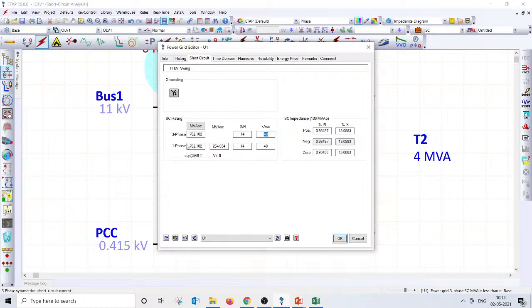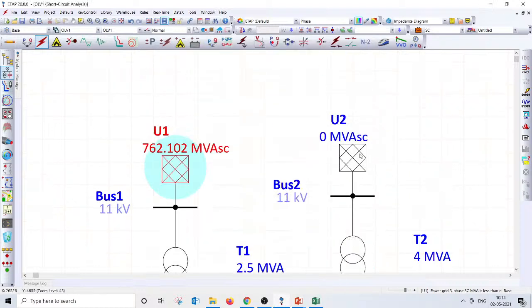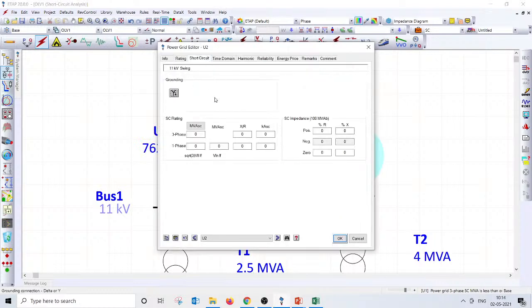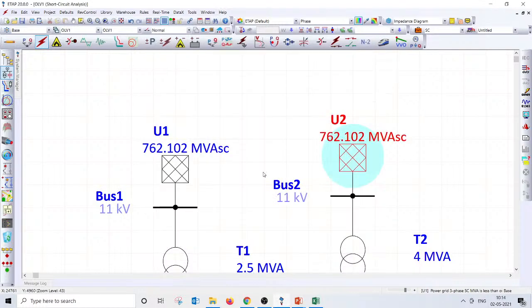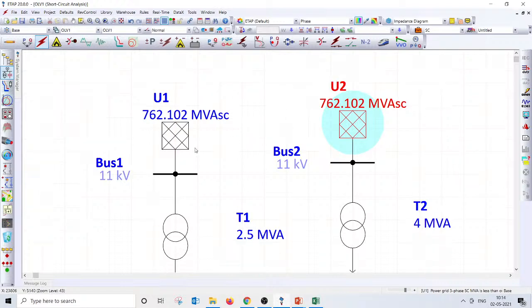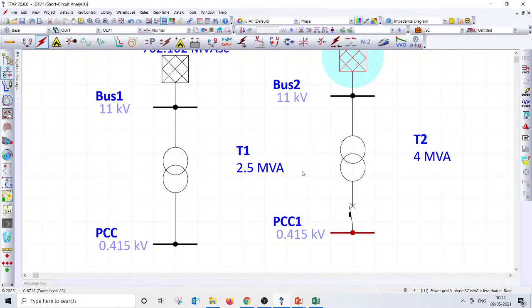Somebody has posted in one of the groups, how to find out the short circuit level at 11 kV in the utility. It's not possible unless you know the upstream information, like where this 11 kV substation is fed from, what the transformer rating is, and what the transformer impedance is, and whether any industries are connected which inject current back to 11 kV. All this information you need to know, and utilities might perform load flow and update the short circuit level at each and every substation every year. So let me go ahead and look at what the short circuit current at the PCC is.